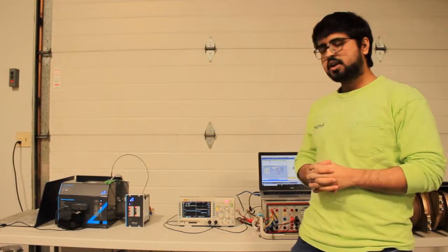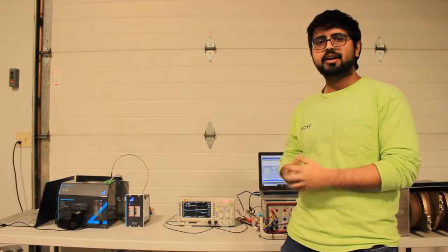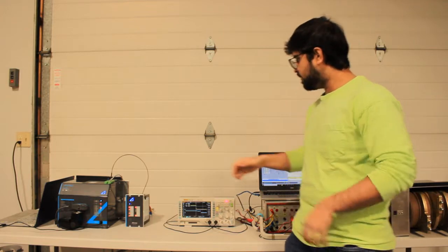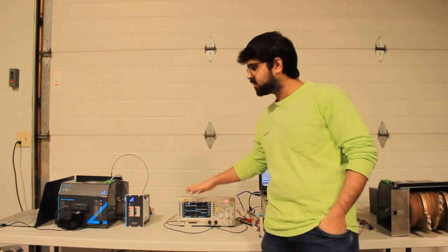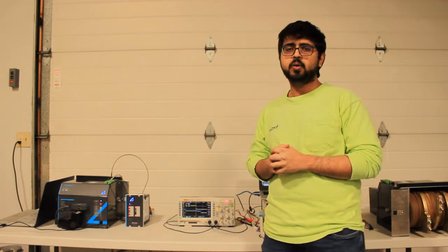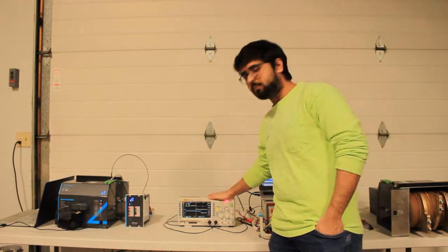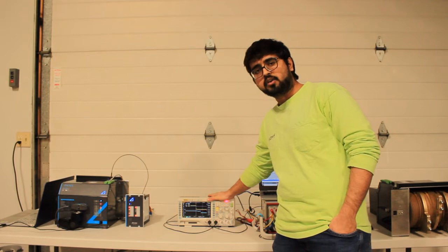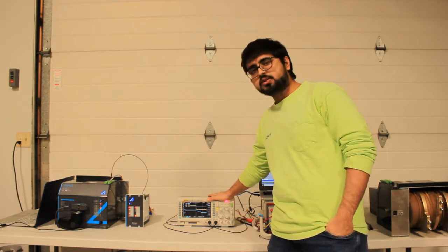We don't really need to use an oscilloscope since Arteche ensures us that it quenches under five milliseconds. It's just to be extra sure and verify the time that the quencher goes off is under five milliseconds.